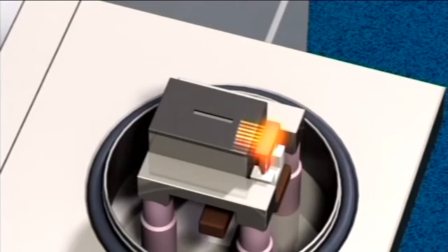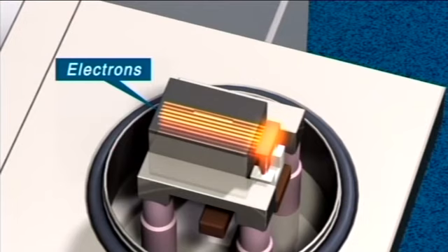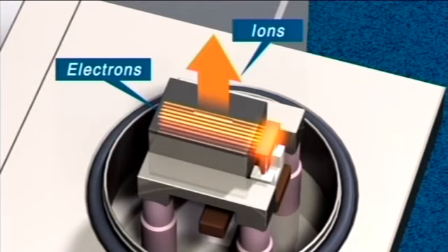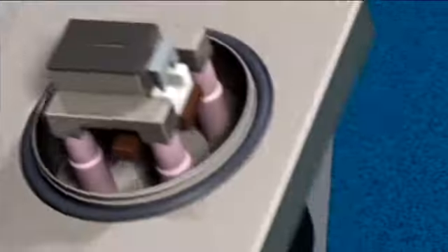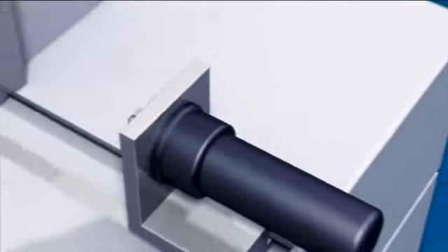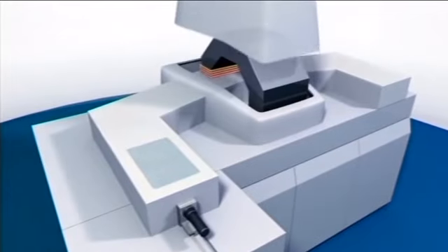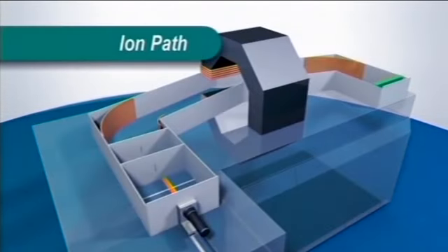Scanning method. When operated in the scanning mode, the mass spectrometer records the mass spectrum of all ions detected within a defined mass range by scanning at predetermined mass intervals. The record of total ion intensity on each scan with time is called the total ion chromatogram, that is TIC.